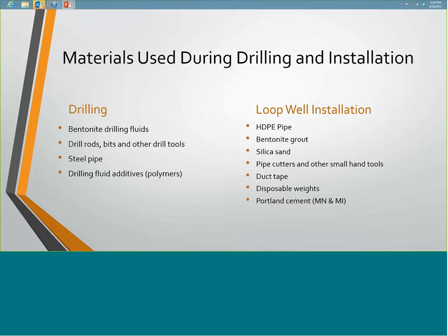In the loop well installation, we've got high-density polyethylene pipe, bentonite grout, and silica sand that you add to the grout to allow the borehole to exchange heat with the formation better. You use a lot of pipe cutters and small hand tools to fit, seal, and cap the pipe. One of the odd things people overlook a lot is duct tape - we use boxes and boxes, probably pallets of it on bigger jobs, for fastening tremie pipes and loop weights. It's actually a product used in quite large volumes.